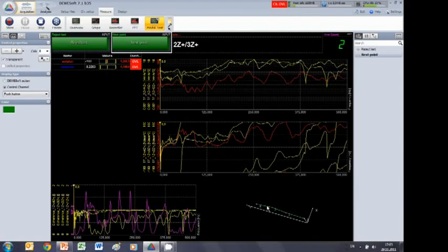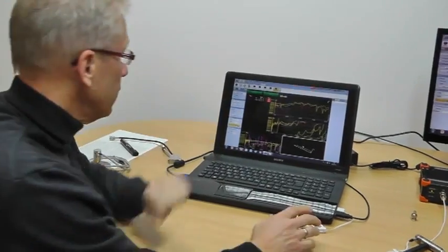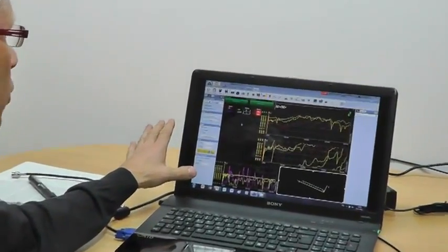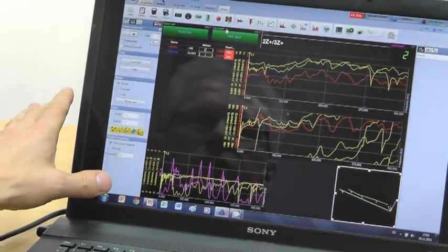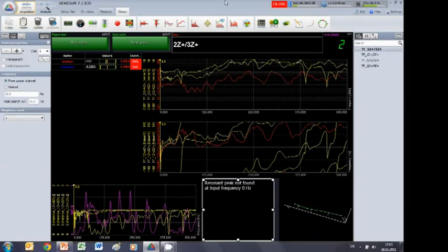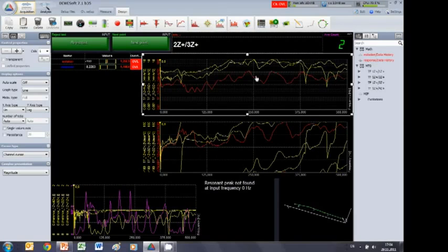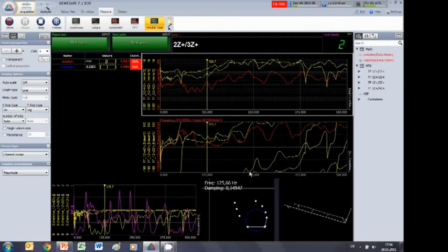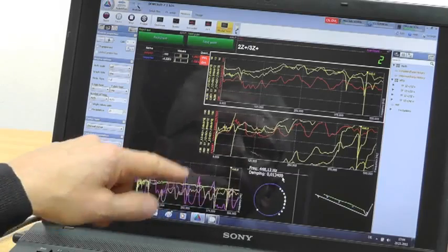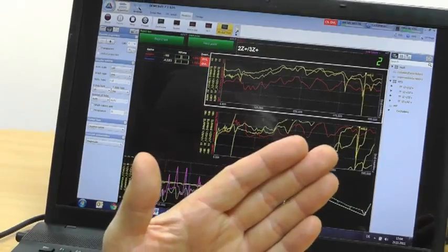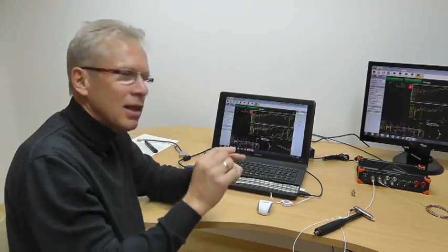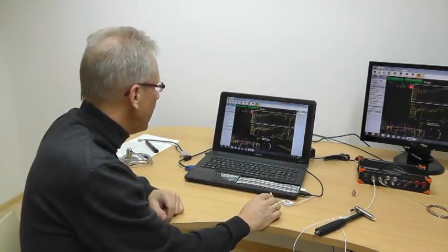But now maybe you want a couple of other things I show you here. Where is my circle fit, you wonder? Okay, let's make the circle fit. You see the model test still has this mark here, which means so far I changed nothing. If I go now to the design mode and change one of these pictures, this disappears, and now I add, for example, my circle fit. This is my circle fit window, where I can go to a certain area and show you the precise frequency. We have a line frequency resolution based on the sampling rate, the record length and the block size, and with the circle fit between the lines we calculate the peak, and therefore we get a higher resolution here.